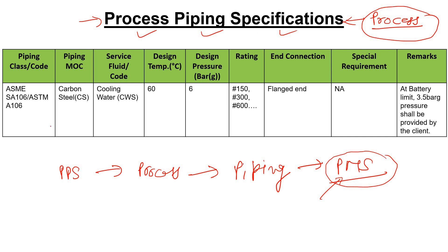Let's take an example. Suppose you are using a cooling water supply line. In that cooling water supply line you are using carbon steel MOC — so the MOC of this pipeline is CS. The piping code is ASME SA106 or ASTM A106. Here, 'class' refers to the code standard, not pressure classes like 150 or 300.